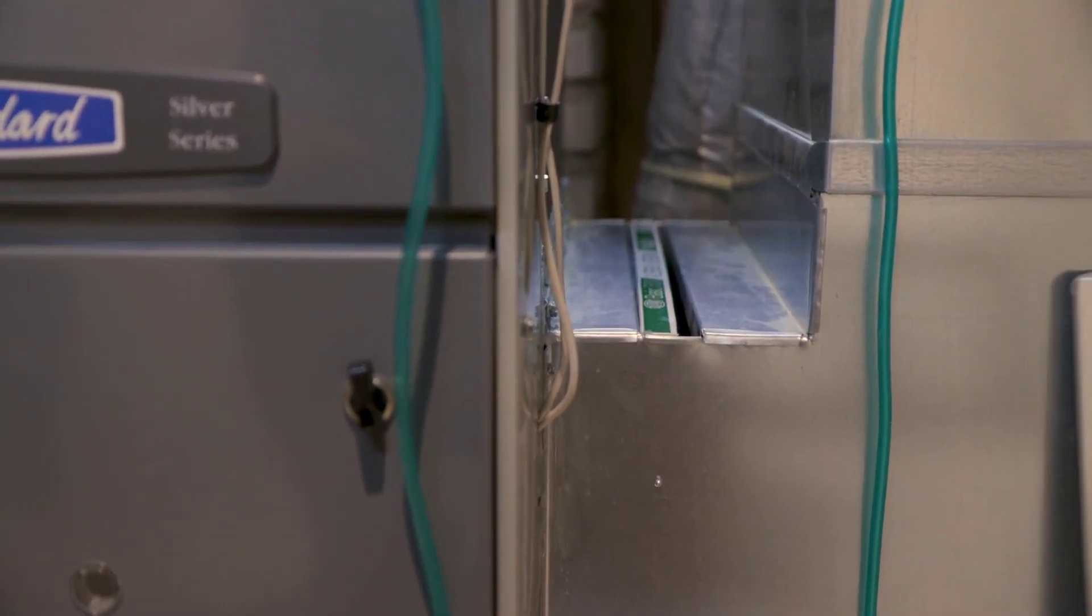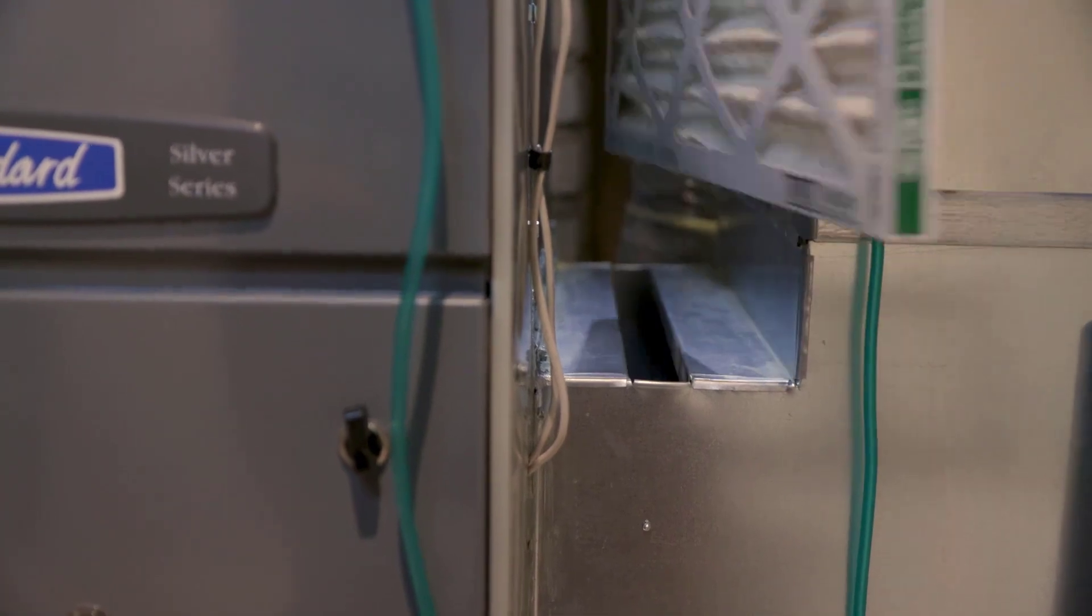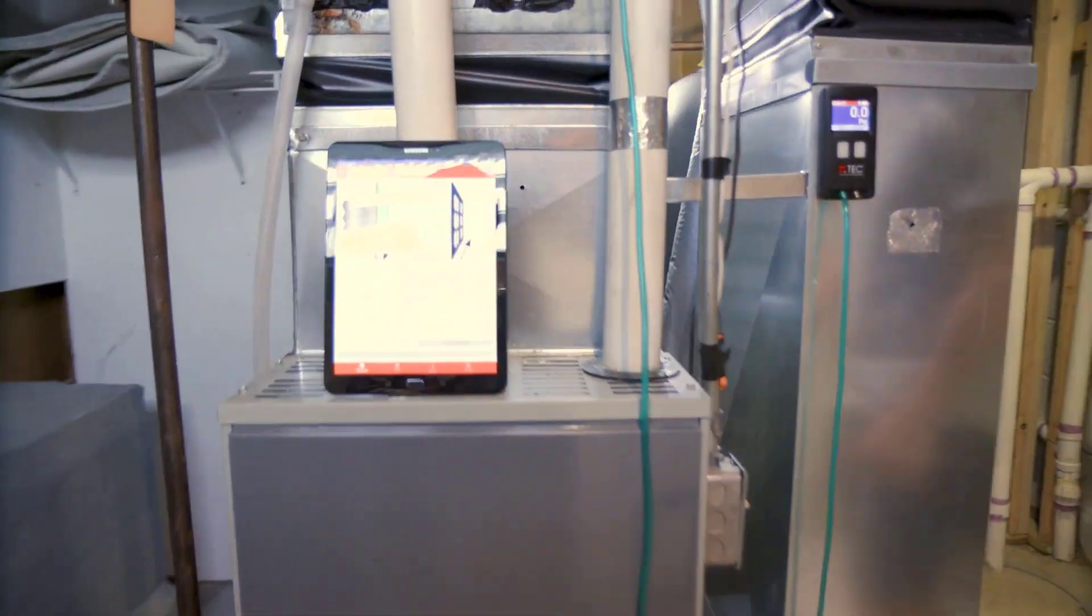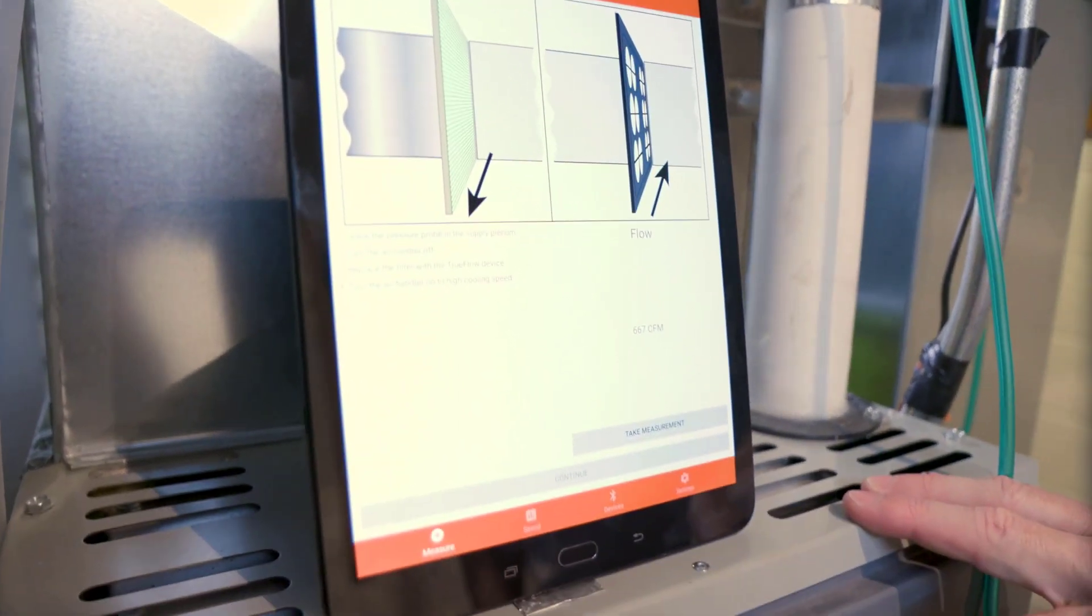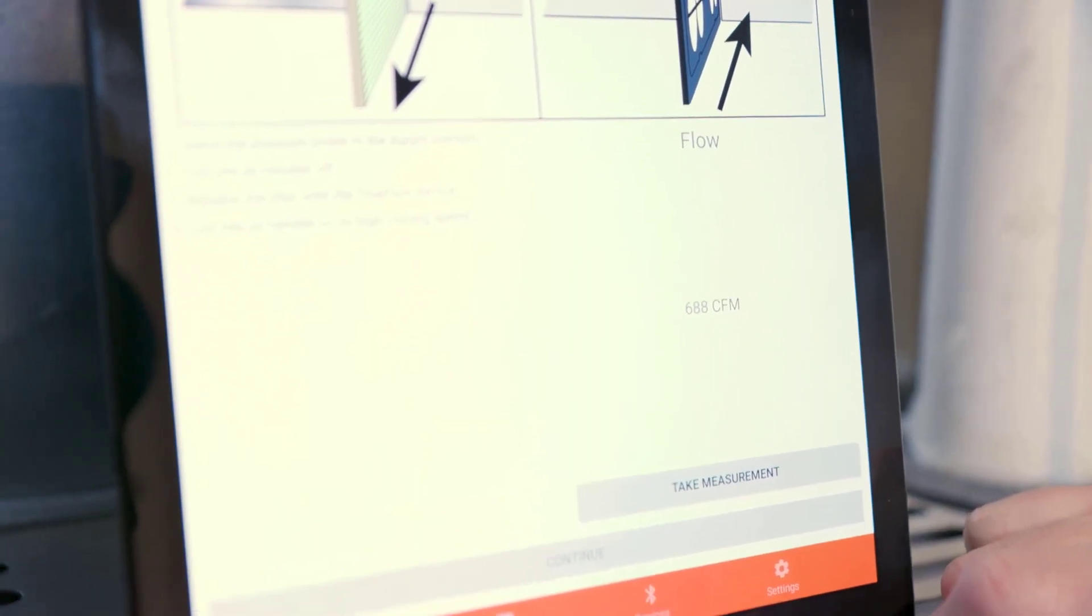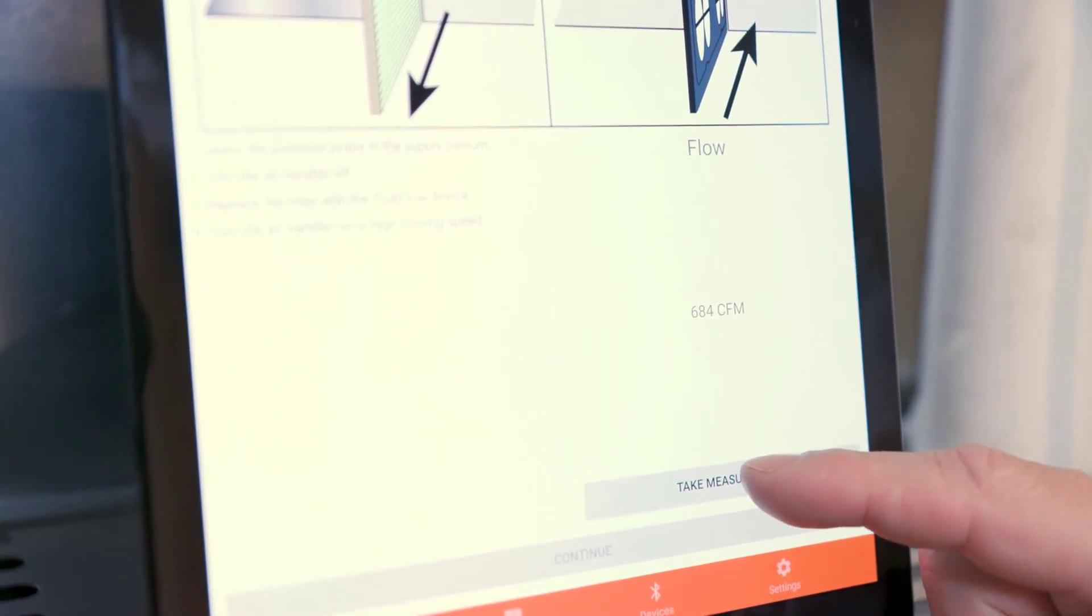Once this is complete, now we're prompted to remove the existing filter. So I'm going to shut the system off, remove the filter cap, take out the existing filter, and slide in the digital TrueFlow plate. Now I'm going to turn the system back on and wait for the fan to turn back on. You'll see we're starting to get a measurement there. Once I see that stabilize, we're then ready to take our measurement.